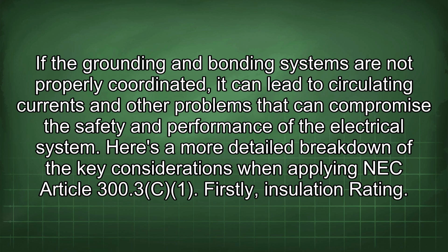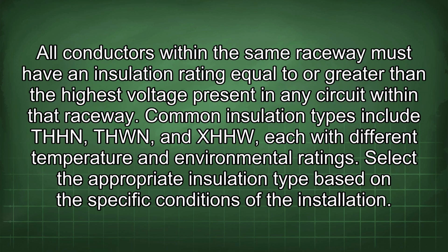Here's a more detailed breakdown of the key considerations when applying NEC Article 300.3(C). Firstly, insulation rating. All conductors within the same raceway must have an insulation rating equal to or greater than the highest voltage present in any circuit within that raceway. Common insulation types include THHN, THWN, and XHHW, each with different temperature and environmental ratings. Select the appropriate insulation type based on the specific conditions of the installation.